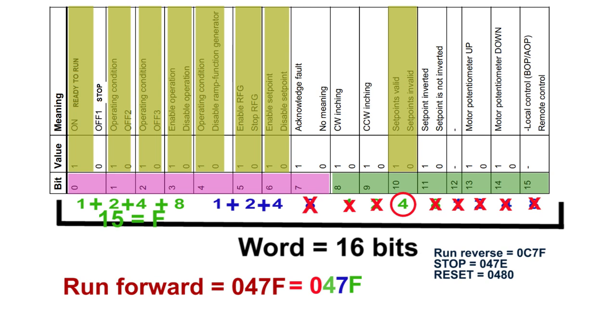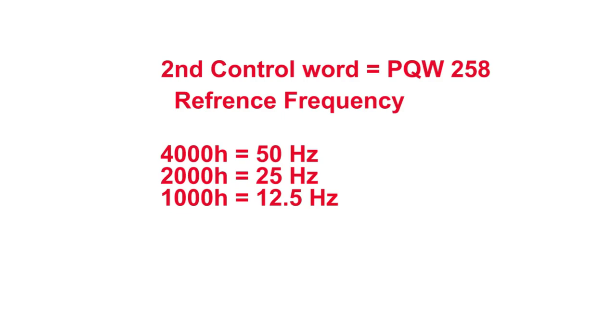These codes are listed in the VFD manual. To run in reverse, the code is 0C7F. To stop the VFD, the code is 047E. To reset the VFD when there is an alarm, we send 0480. These are the four most commonly used codes. The second control word — PQW 258 in our case — is used for the reference frequency. If we send 4000 hex, the motor runs at 50 Hz; 2000 gives 25 Hz; 1000 gives 12.5 Hz.